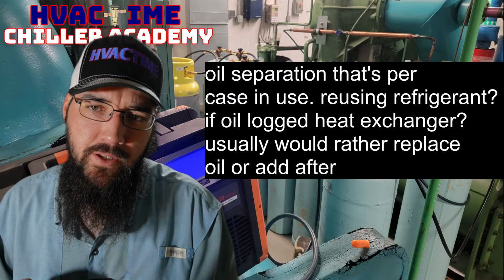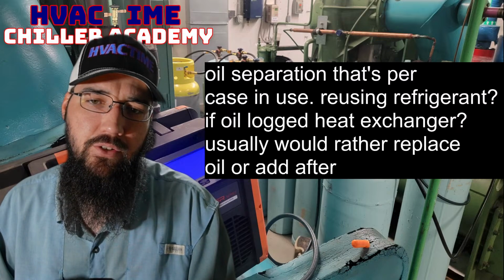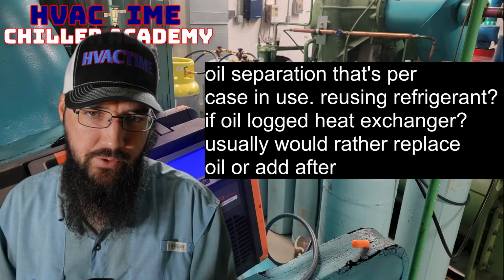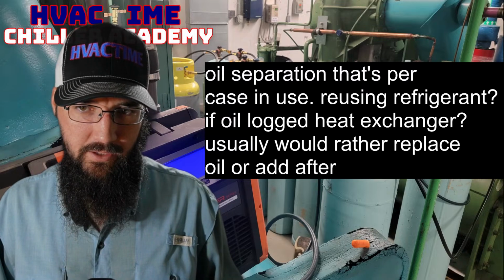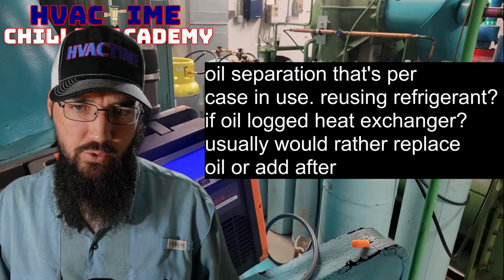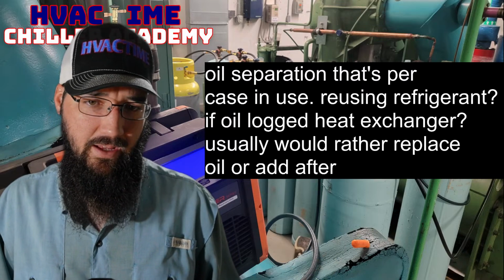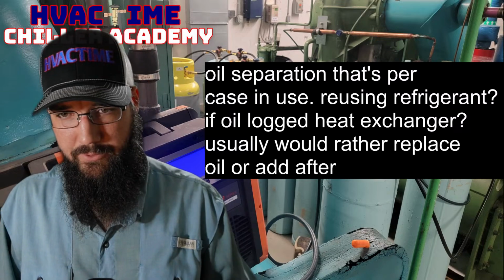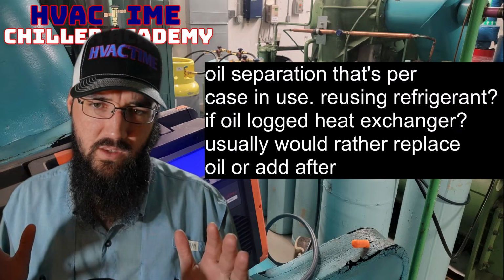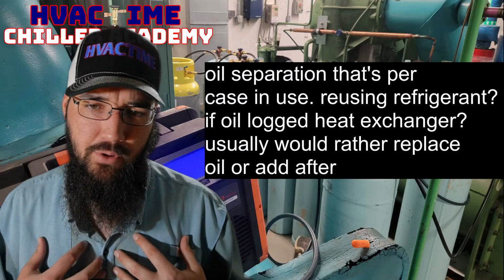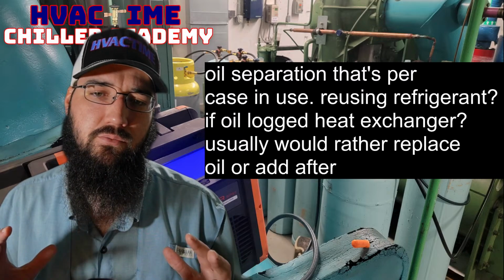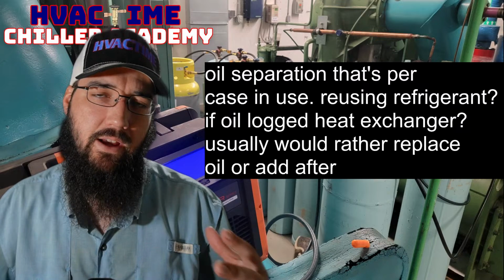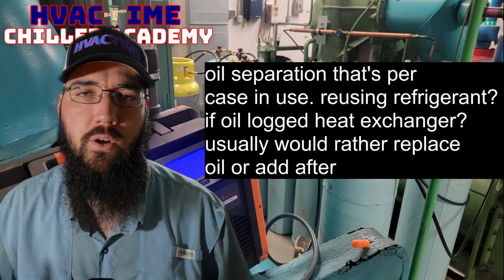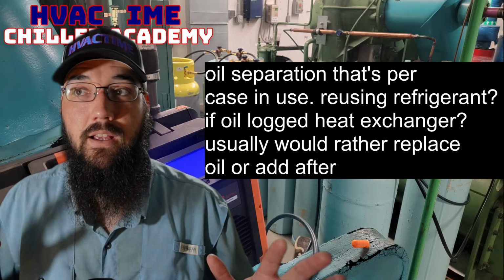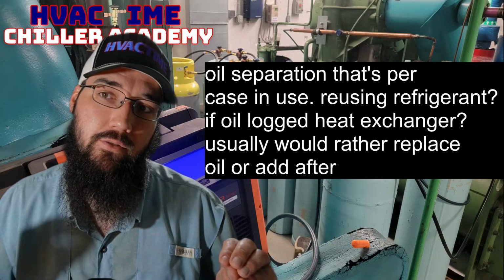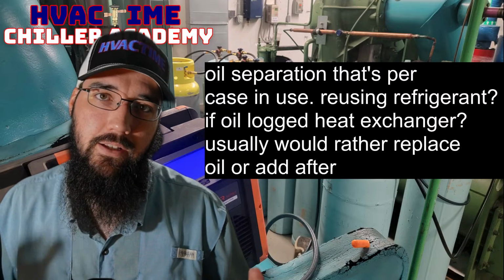Oil separation, that's per case in use. Reuse refrigerant if oil-logged heat exchanger. Usually would rather replace oil or add after. So I personally would much rather replace that oil, if I have to, whatever oil amount it was, while it could literally be majority of your oil charge. Ideally it wouldn't be.